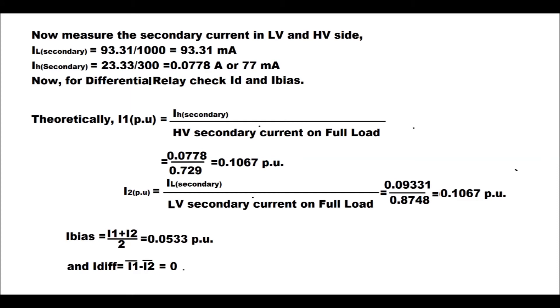Now measure the secondary currents on the LV and HV sides. The LV secondary current = 93.31 / 1000 (since CT ratio on LV side is 1000/1) = 93.31 milliamperes. The HV secondary current = 23.33 / 300 (since CT ratio for HV side is 300/1) = 0.0778 amperes, or 77 milliamperes.